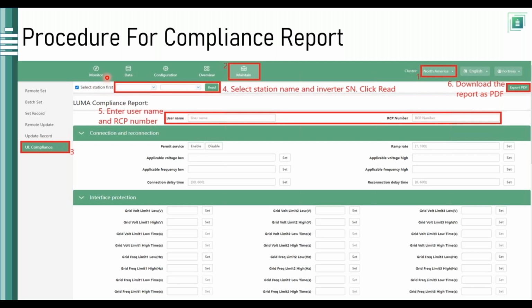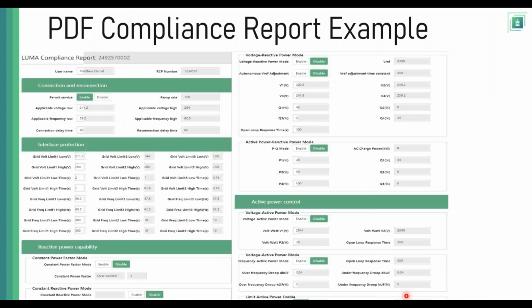Here is a kind of utility compliance report that some jurisdictions do mandate, and we facilitate that through our web portal. All you have to do is go on the web portal with your installer credentials, and these are your main sections: monitor, data, configuration, overview, and maintenance. You select maintenance, you select the UL compliance, you select the station, and you press read to read all the configurations that you've installed when you programmed the inverter. It will read the grid voltage and frequencies according to that region. Then you put the customer or end user's name here, and then your utility account, and you press export PDF, and it will generate a compliance report.